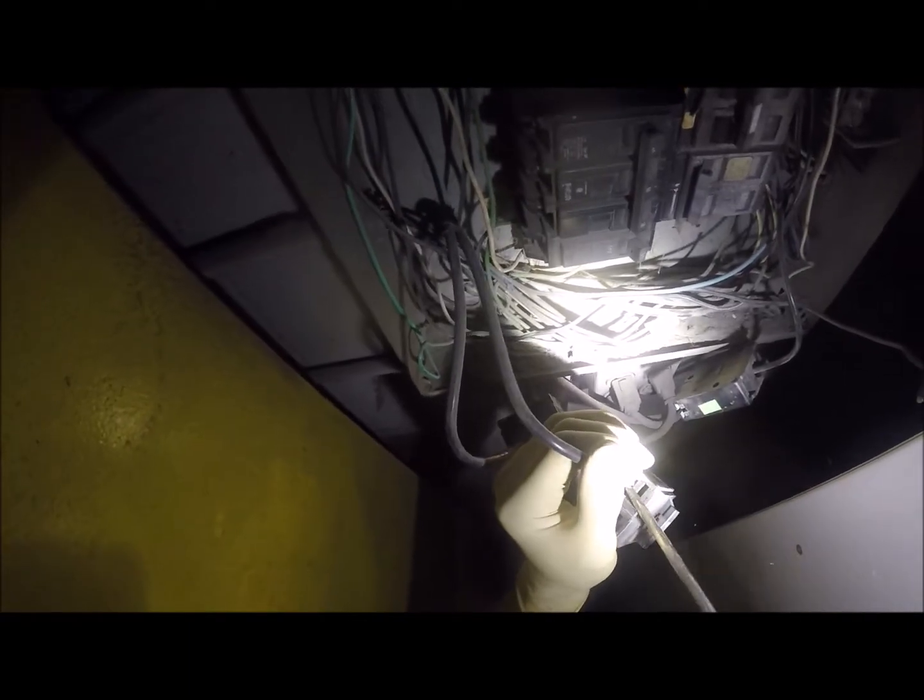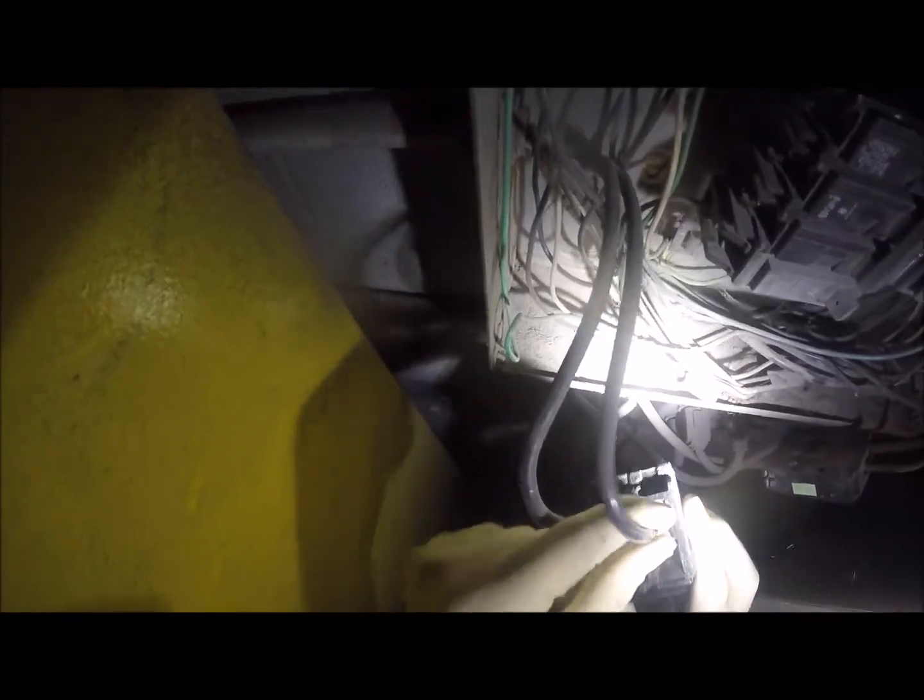And I also think that the whole cause of this was breaker failure. It does happen throughout the years. Maybe I need to change that 30 too. That one's looking kind of old. But before I get to that side, actually before I stick the 60 in, I'm going to put the electrical paint on that circuit there.